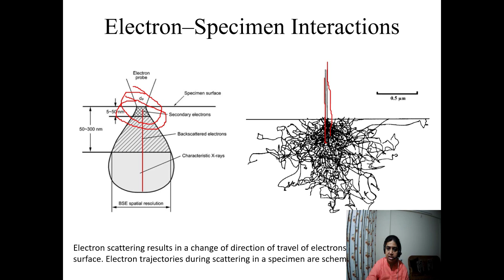Here the secondary electrons travel with large deflection towards the detector. However, the back scattered electrons travel directly towards the detector. Again, there is a Faraday cage in front of the detector itself. If it is negatively charged, what will happen? The secondary electrons ejected have very little energy, just a few eV, so they will be stopped. However, back scattered electrons will reach the detector. In this way, just by changing the potential applied to the Faraday cage, we can select whether we detect secondary as well as back scattered electrons.